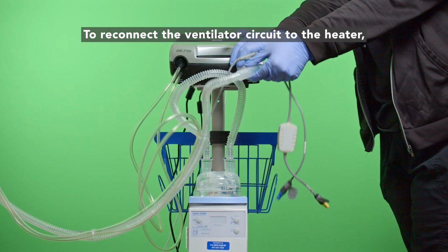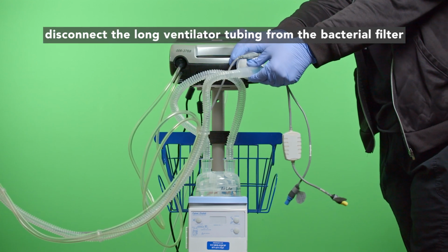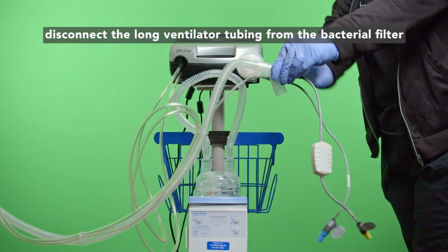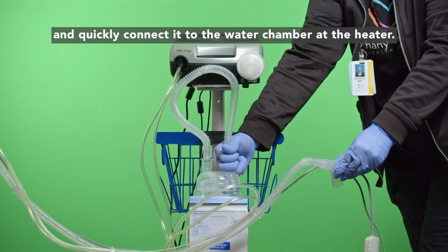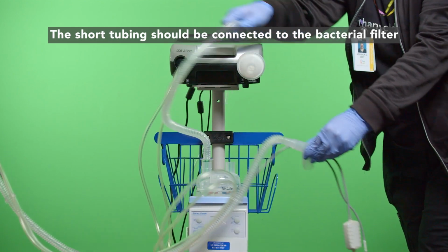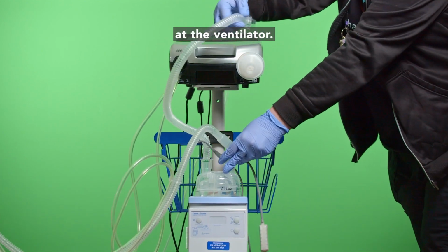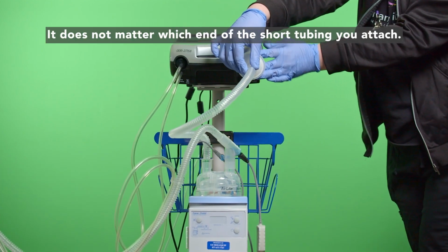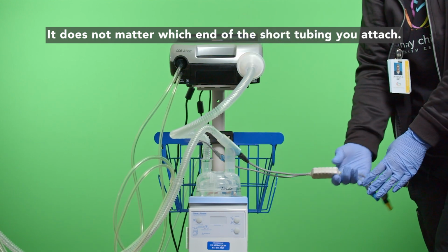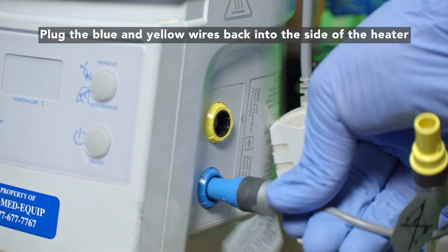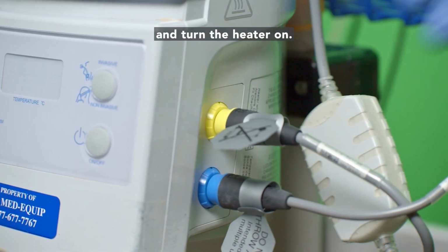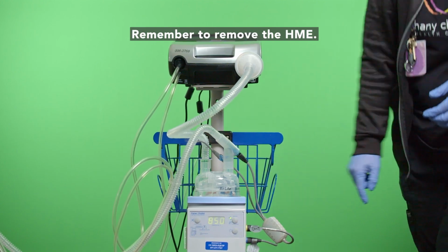To reconnect the ventilator circuit to the heater, disconnect the long ventilator tubing from the bacterial filter and quickly connect it to the water chamber at the heater. The short tubing should be connected to the bacterial filter at the ventilator. It does not matter which end of the short tubing you attach to the ventilator. Plug the blue and yellow wires back into the side of the heater and turn the heater on. Remember to remove the HME.